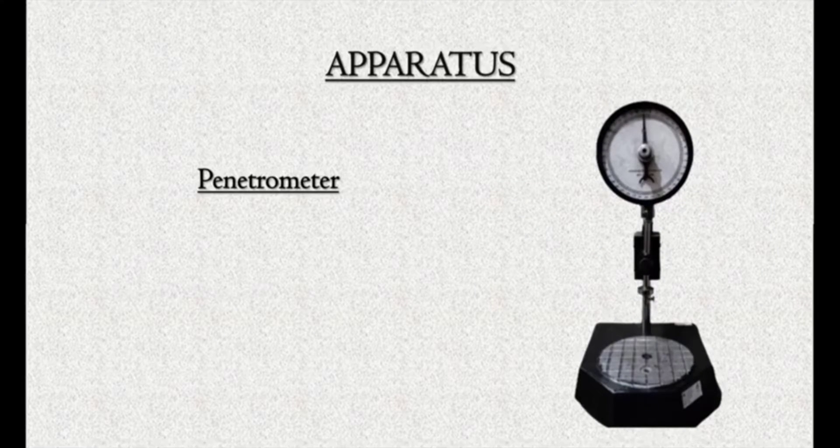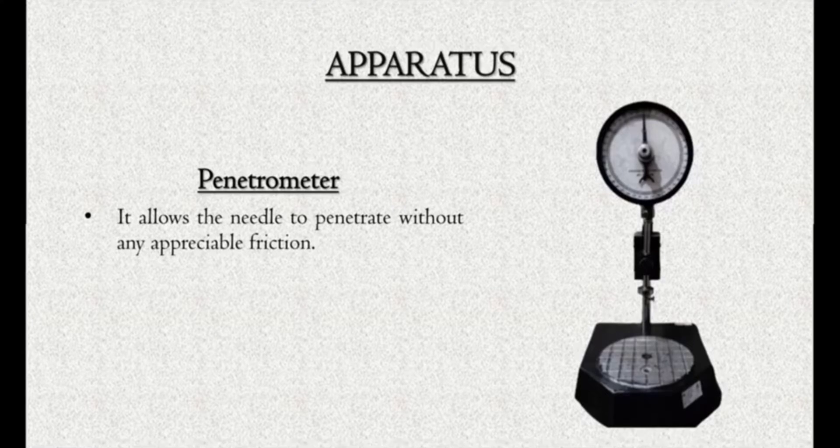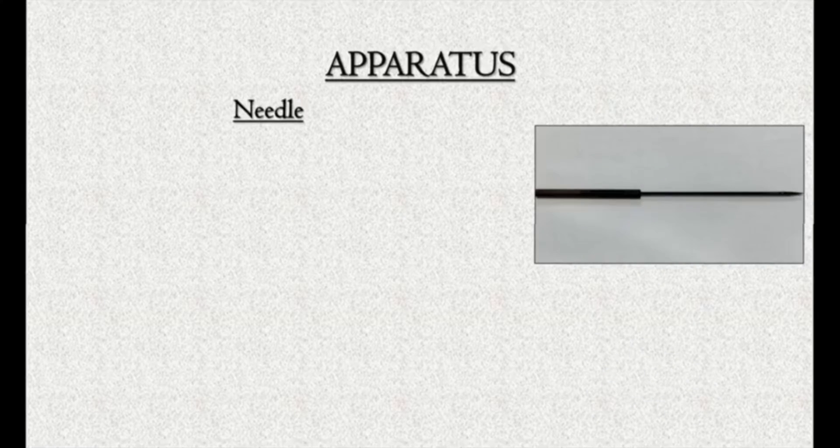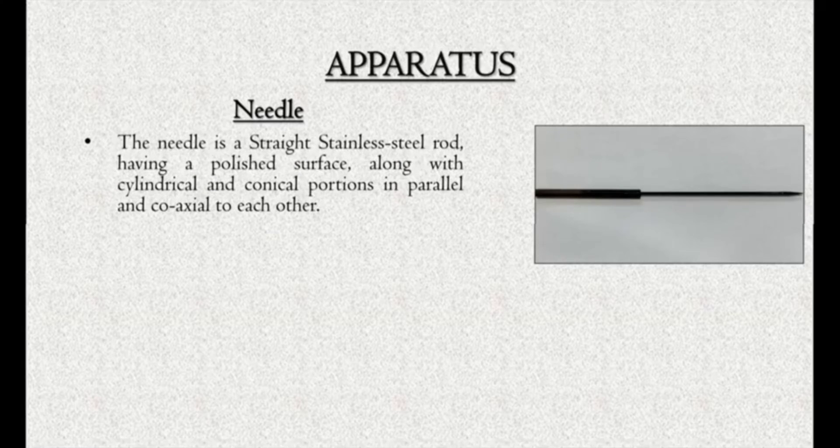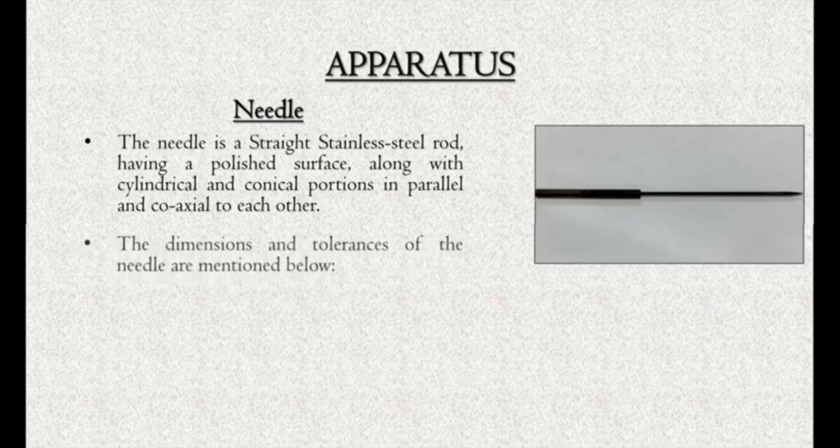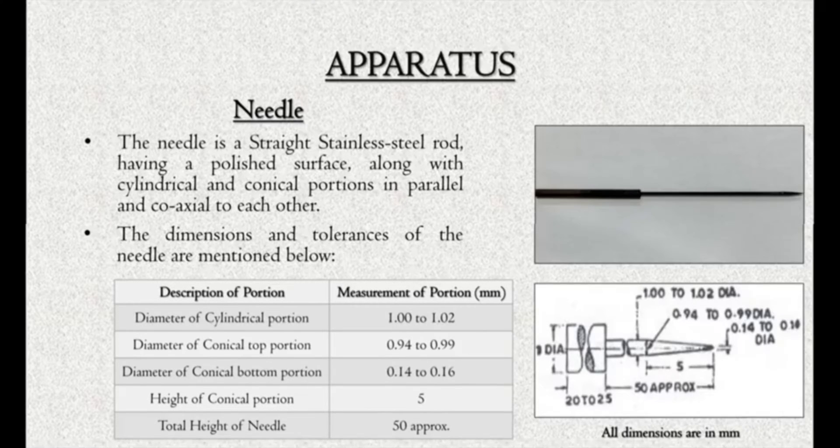Penetrometer: It allows the needle to penetrate without any appreciable friction. Its accuracy is measured in one-tenth of millimeter. The needle is straight, stainless steel rod having a polished surface along with cylindrical and conical portions parallel and coaxial to each other. The dimensions and tolerances of needle are mentioned below: Diameter of cylindrical portion, diameter of conical portion, diameter of conical bottom portion, height of conical portion, total height of needle.